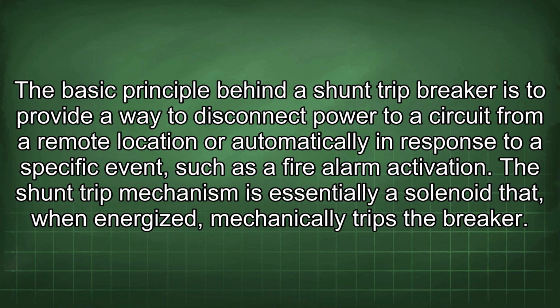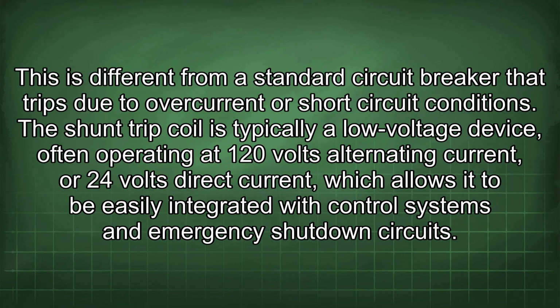The shunt trip mechanism is essentially a solenoid that, when energized, mechanically trips the breaker. This is different from a standard circuit breaker that trips due to overcurrent or short circuit conditions. The shunt trip coil is typically a low voltage device, often operating at 120 volts alternating current or 24 volts direct current, which allows it to be easily integrated with control systems and emergency shutdown circuits.